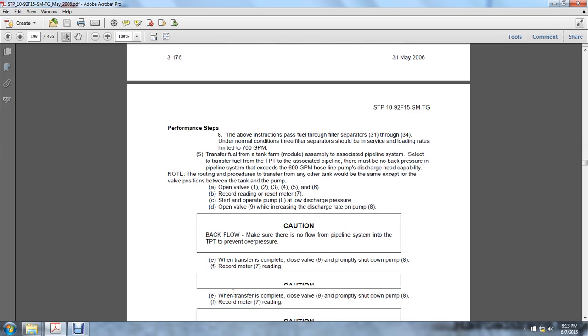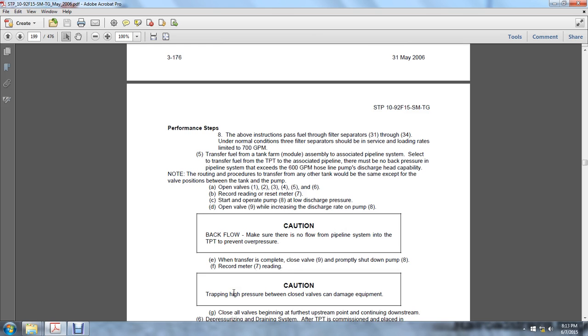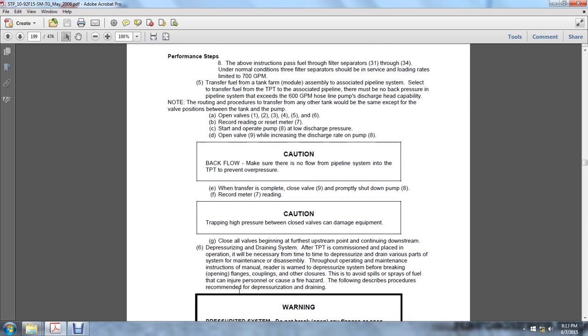Prevent overpressure. When transfer is complete, close valve 9 and properly shut down pump 8. Record the meter at 7. Trapping high pressure between closed valves can damage the equipment. Close all the valves, beginning at the first upstream point and continuing downstream.